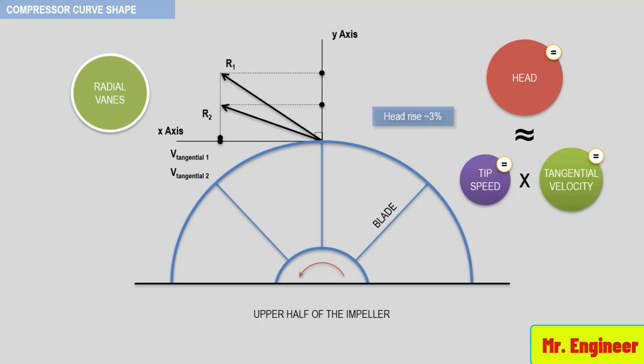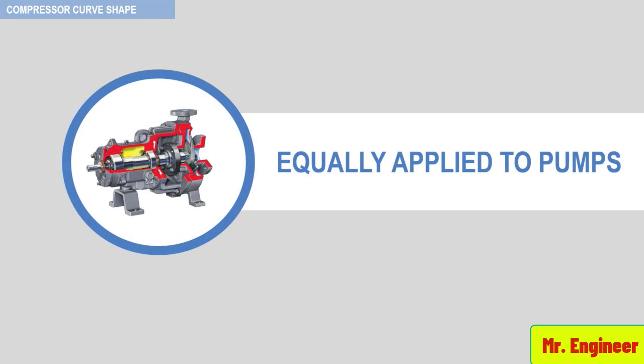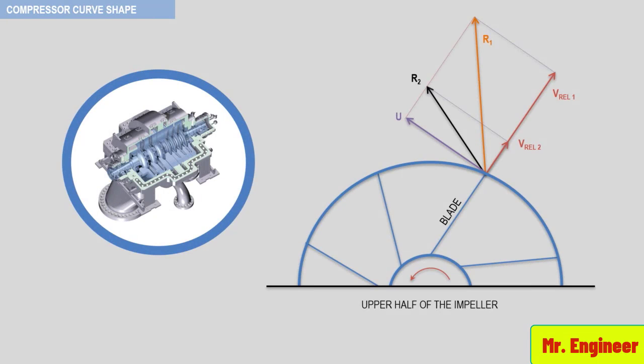In summary, the previous discussion can be equally applied to pump impellers, since pumps also operate on a fluid — in this case a liquid. The only exception is that, regardless of the type of liquid, the velocity relative to the blade will never change since the liquid is incompressible. In the case of a centrifugal compressor, however, the gas is compressible, and the velocity relative to the blade at the discharge will change as a result of the pressure and temperature of the gas at the exit. Therefore, the statement that head produced by a compressor impeller remains constant at a given speed is not totally true.